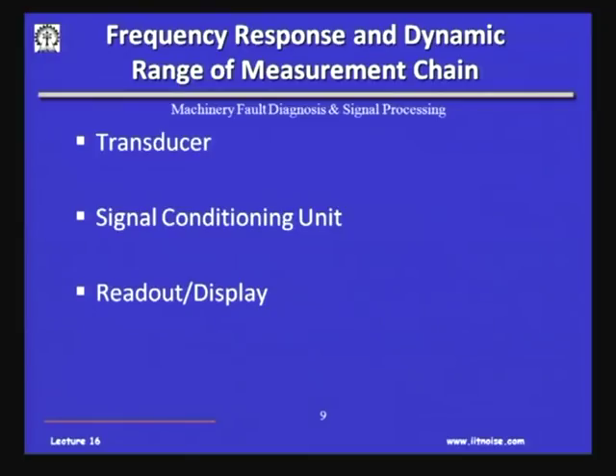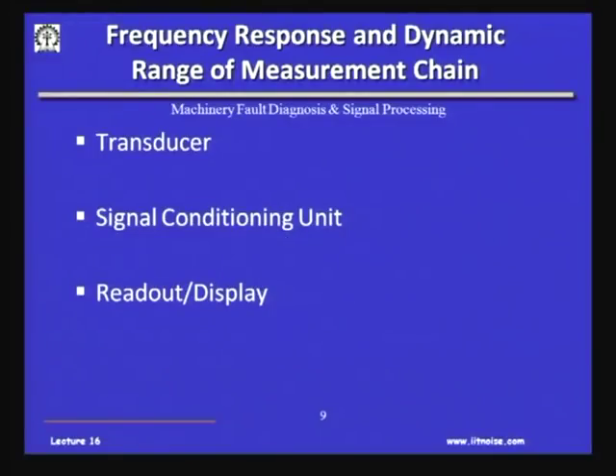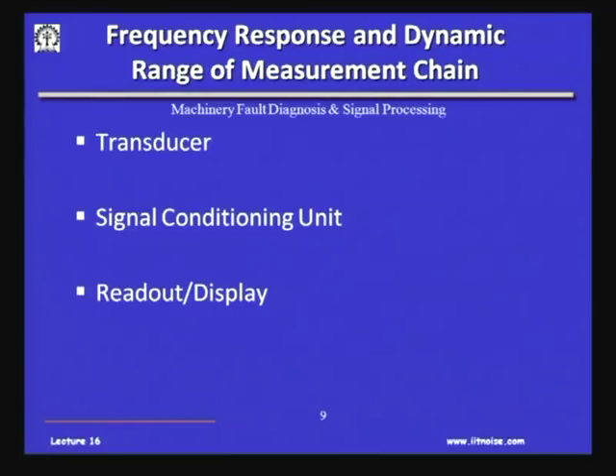When talking about the entire measurement chain — if a transducer has a good frequency response of 10 kHz, but the signal conditioning unit responds up to only 5 kHz, and the digital display only up to 2 kHz — I cannot claim I have a 10 kHz bandwidth of measurement. That is an important mistake people make. We have to keep in mind the frequency range and dynamic range of the entire measurement chain. Dynamic range is the ratio of the highest to the lowest values the same sensing element can sense.